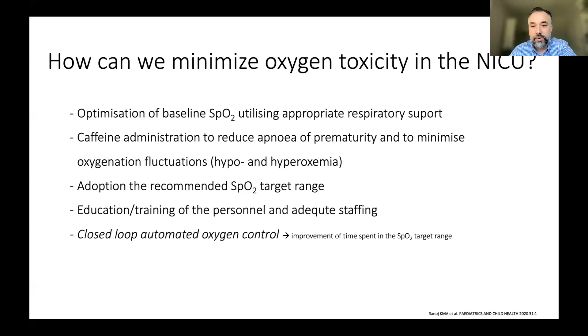So the basic idea is quite simple. In a traditional setup, we would have a pulse oximeter attached to our patient, and based on the readings, based on the alarms, we would come to the ventilator and change the FiO2 setting on the blender until we reach a value which is in the range. When we use an automated system, the pulse oximetry module is connected, or usually is a part of the ventilator, and there is an inbuilt algorithm that provides this intervention for us. So in other words, if the saturation goes below or above the targeted range, the FiO2 setting will be automatically changed by the algorithm.